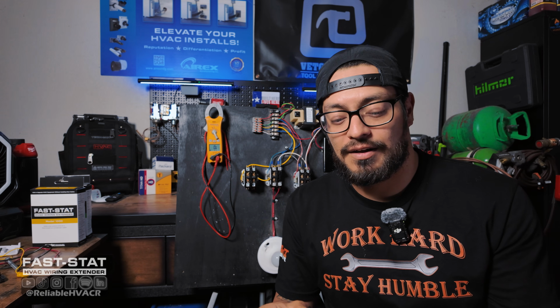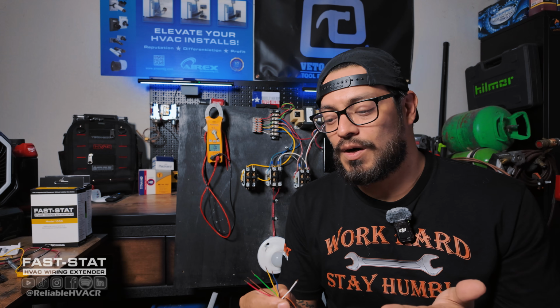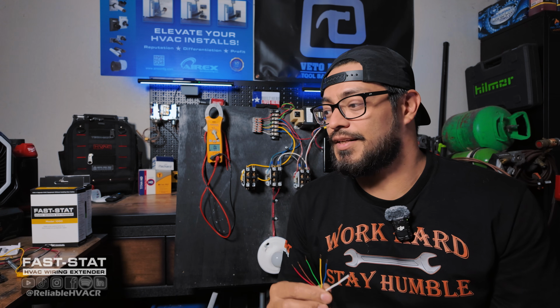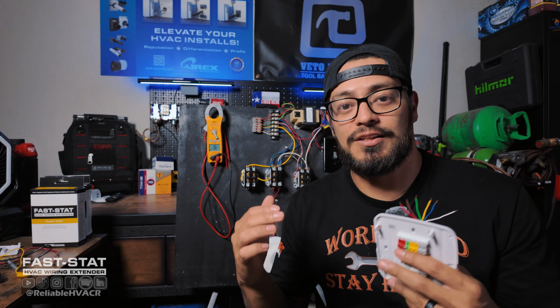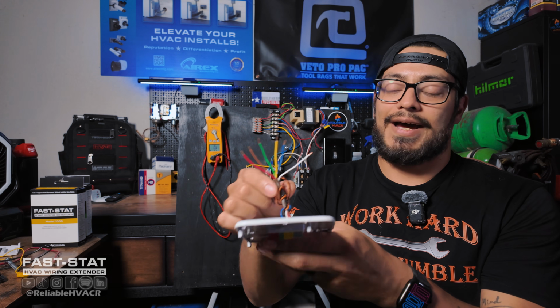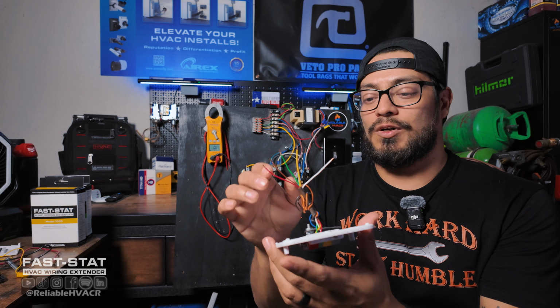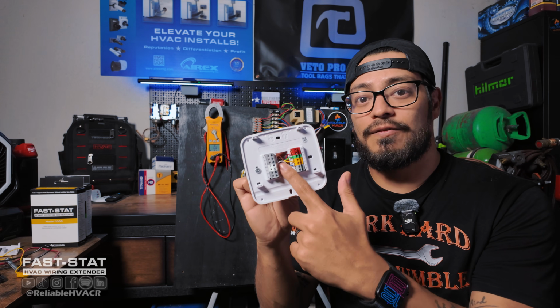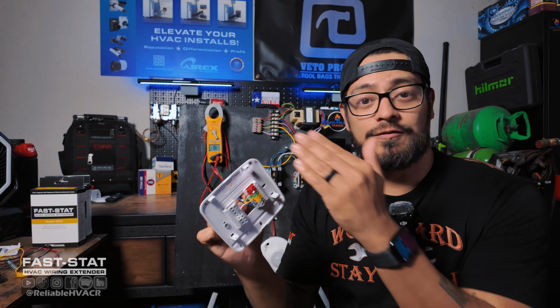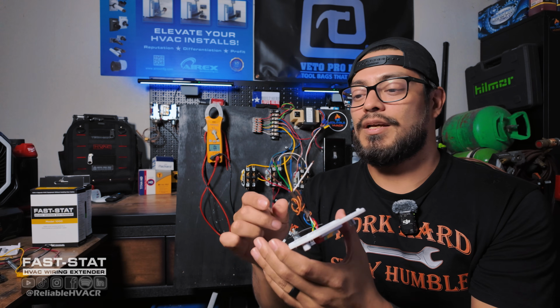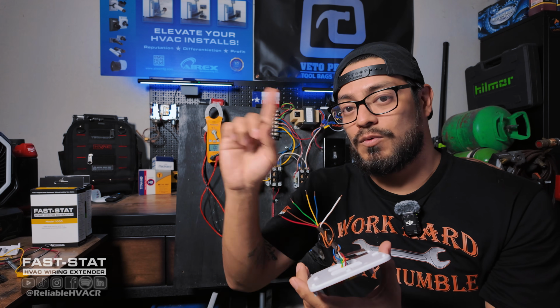When you're looking for a short, obviously you isolate it, you get that short to ground with the meter, and you figured it out that way. How do you find a broken wire? If you suspect a broken wire, let's say you think everything's good, your thermostat's good, and you're still not getting that calling out to the control board or the contactor, wherever it lands, you can also isolate the wires again. You want to actually remove them off of this wall plate. Make sure they don't fall into the wall. Make sure you kind of pull them out. And also isolate them where they land.